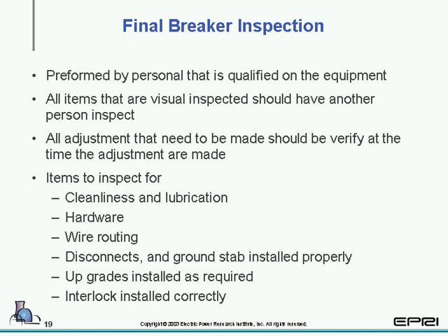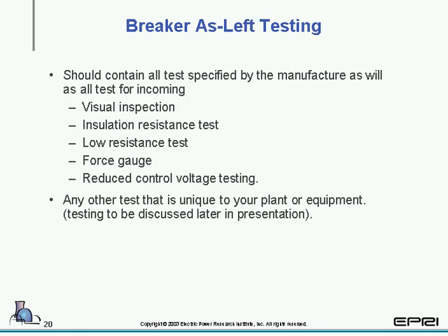And that all adjustments that need to be made should be verified at the same time the adjustments are made. Now what we're saying here is that the second item is that the inspection should be made by another person. If they cannot be, then item 3, or the third bullet down, they should be verified at the same time the adjustments are made. And again, we took a look at some of the items for inspection: cleanliness, hardware, wire routing, disconnects, upgrades, interlocks. And then breaker as-left testing.